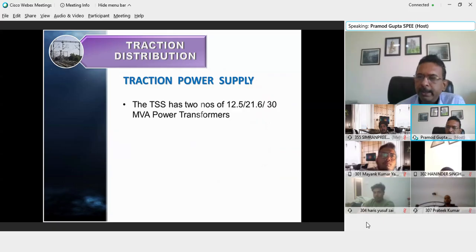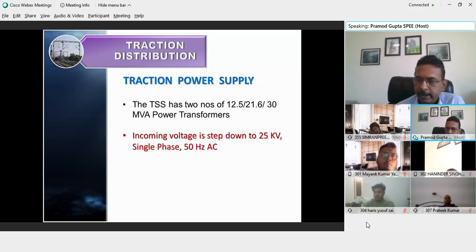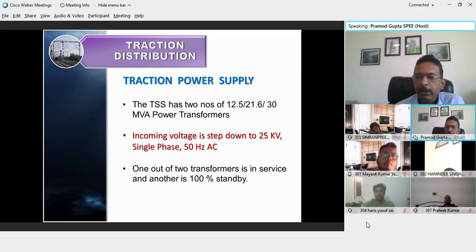Now the TSS has two transformers. The minimum rating is 12.5 MVA and the maximum rating currently available on Indian Railway is 30 MVA power transformer. The dedicated freight corridor is using 60 MVA power transformers in their substations. The incoming voltage steps down. One of the two transformers remains in service. The other transformer is 100% standby. We are using only one transformer at a time, and the other takes over when we want to do some maintenance on the transformer which is in service.